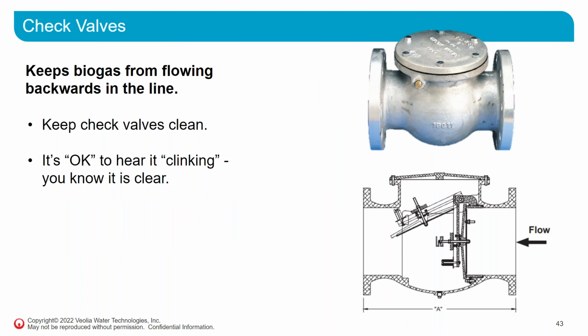We have check valves in the system. I guess not flame check valves, these are just check valves. We'll get to the flame check valves in a minute. Biogas check valves keep the biogas from flowing backwards in the line. It's important to keep these clean so that they perform their duty. It's okay if you hear them making noise. They may clink. Biogas flow isn't necessarily consistent in the system. So as the flow volume changes, the valve will open more or less. So the clinking shows that it's behaving as expected. If you have consistent flow, you may hear it less, but either way is fine.